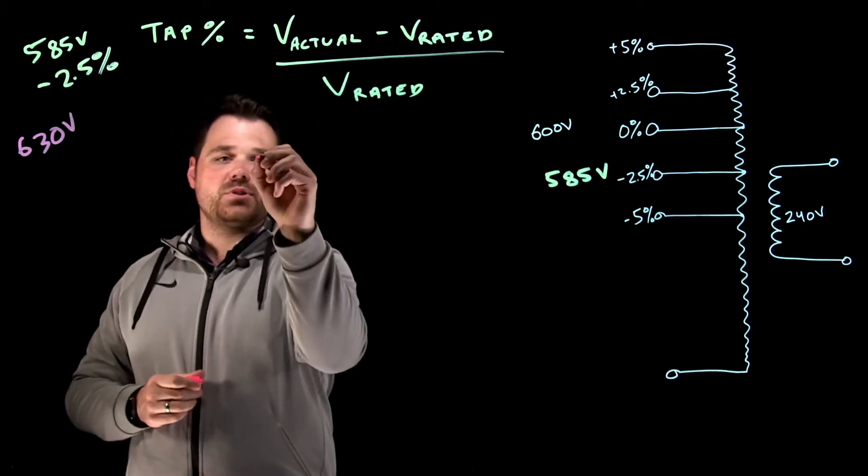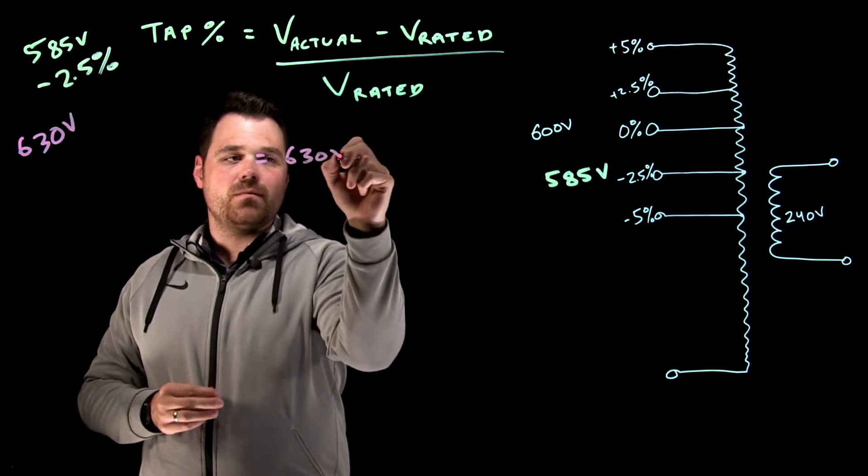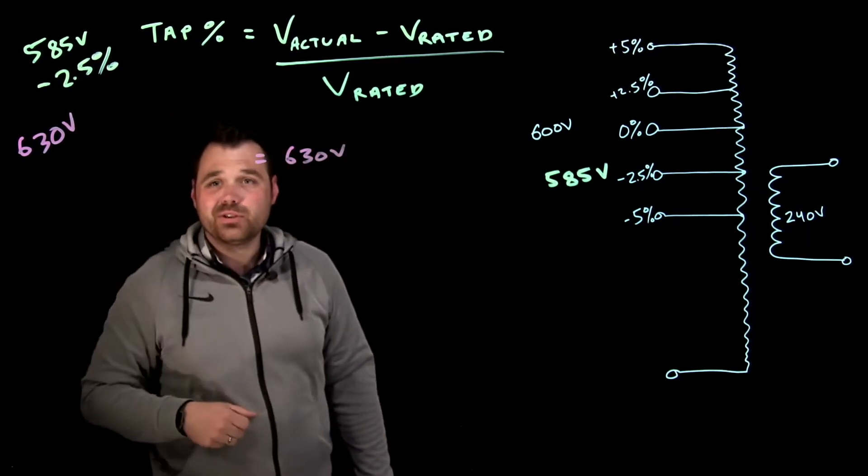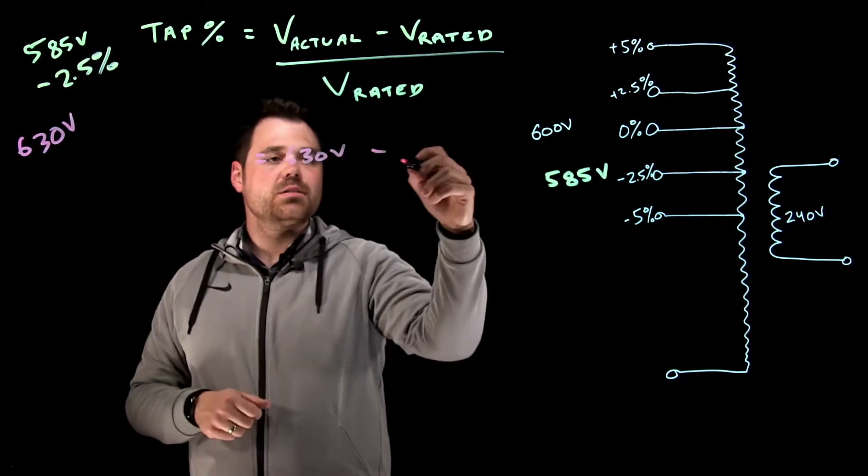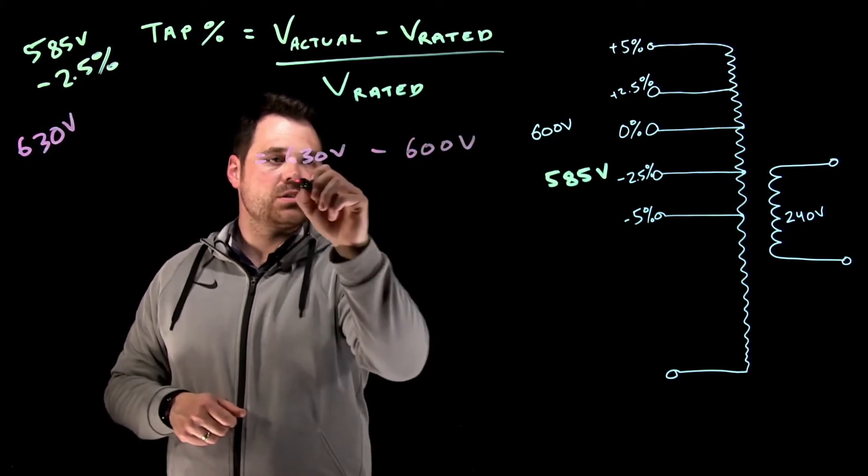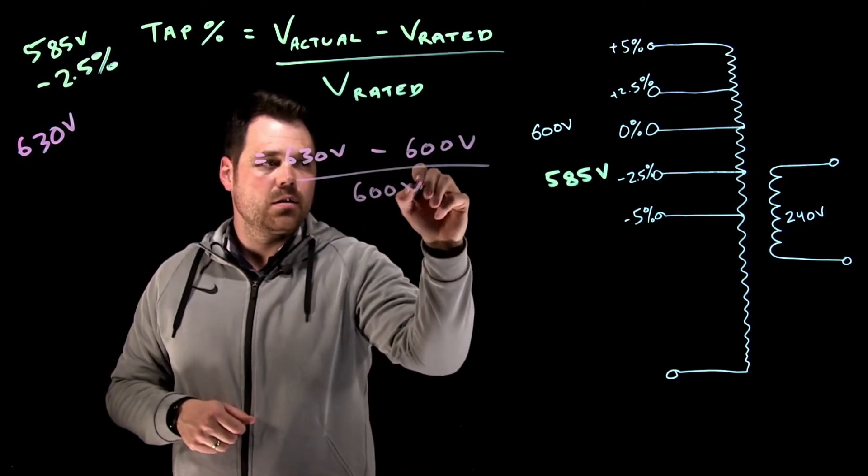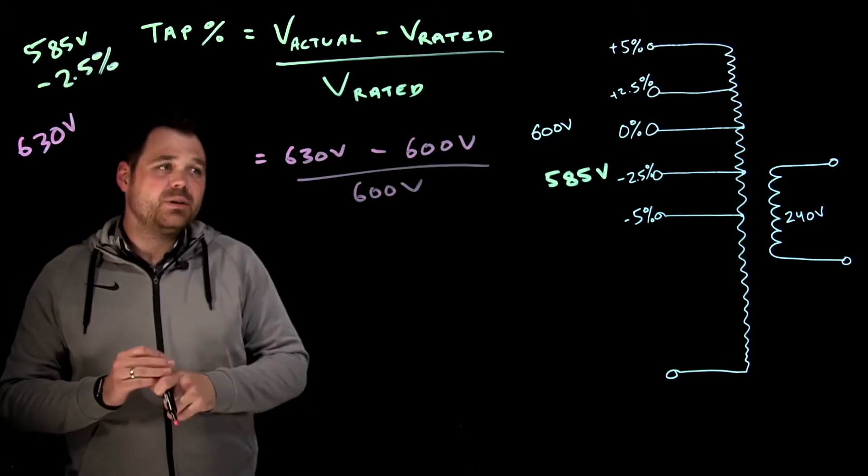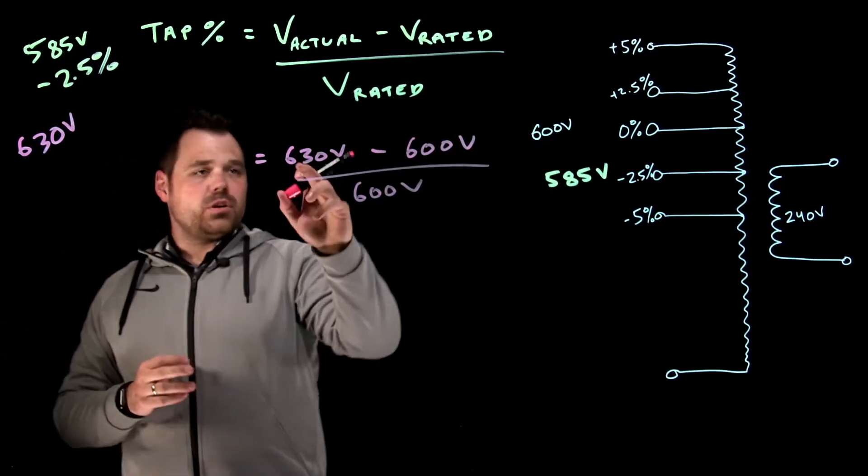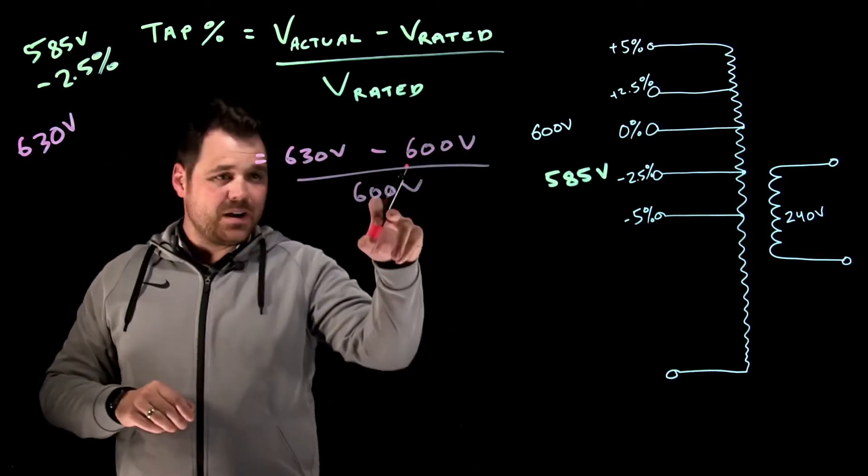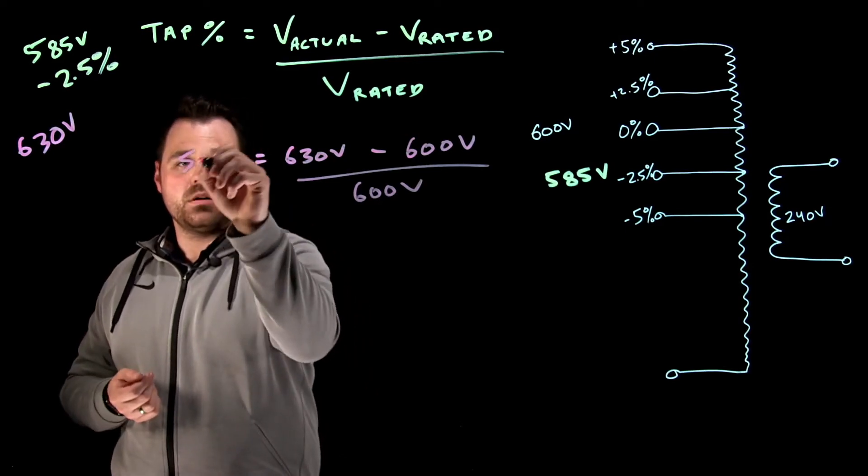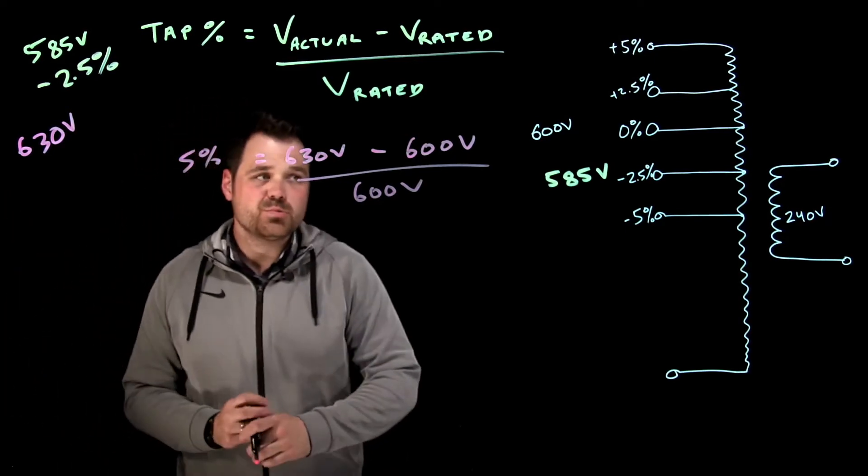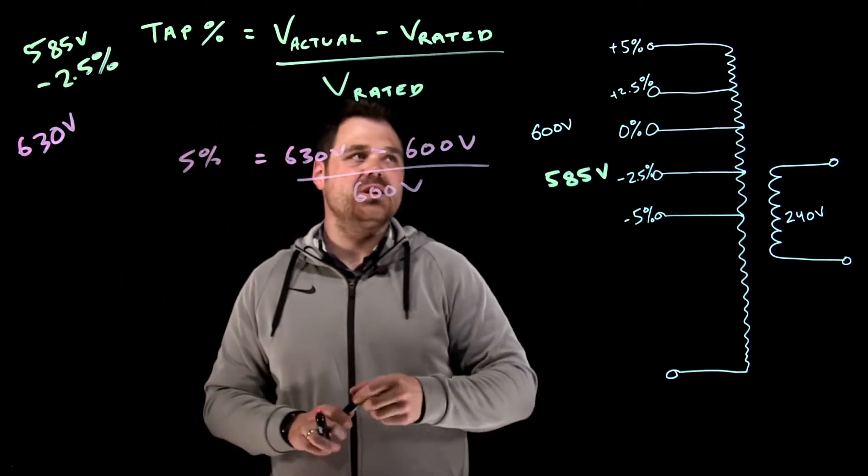Okay, so I'm going to go tap percentage equals 630 volts, my actual voltage minus my rated 600 volts divided by rated. That's going to give me an answer. 630 minus 600, that's 30 divided by 600. That is going to equal positive 5%. So I can use my positive 5% tap.